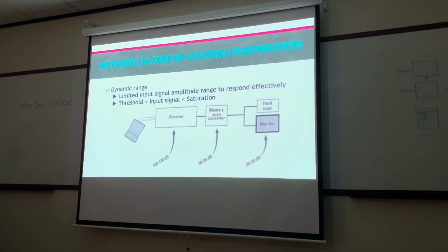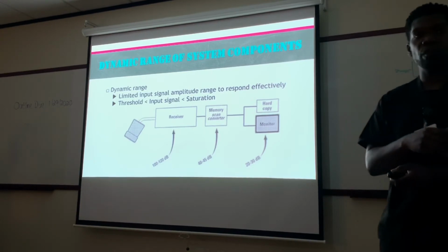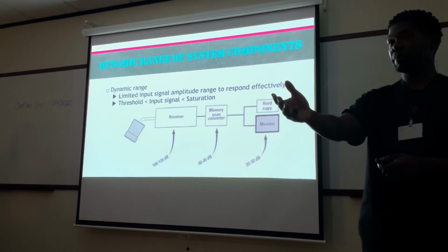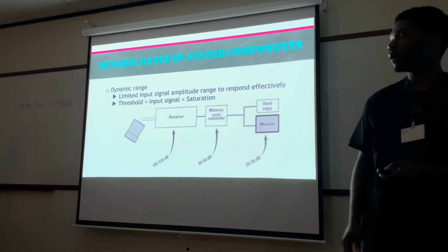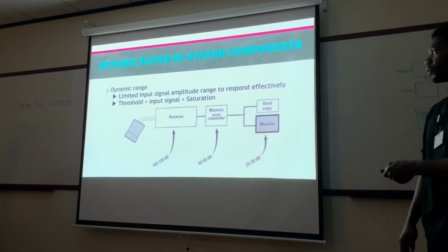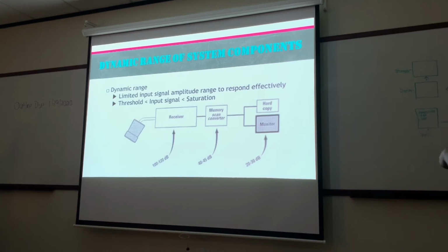Okay. So again, we have our transducer right there. Information, we know, comes back to the beamformer, right? First, that beamformer has a switch that protects the system components, protects the receiver specifically, from those high voltages from when the beam is being transmitted. Okay, so after it goes transducer, beamformer, back to the beamformer right there, then to the receiver, then it has the scan converter.